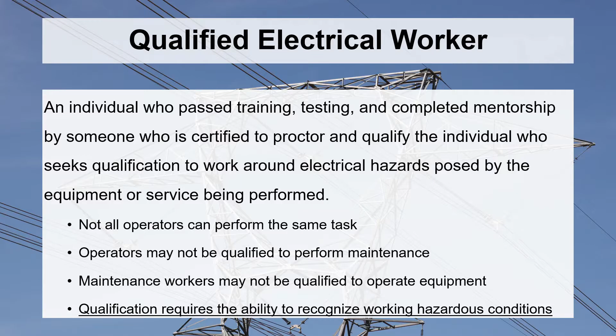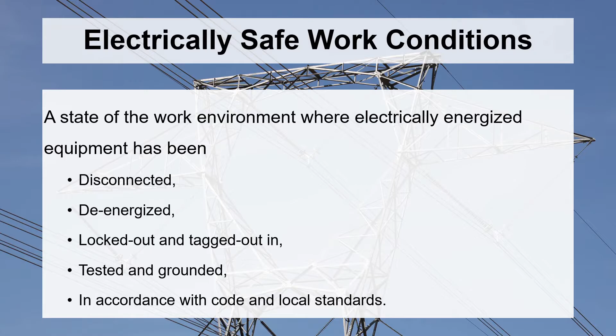Following the principles of electrical safety, creating a safe work environment means that any hazardous energy source is disconnected, de-energized, locked out and/or tagged out if needed, and tested to prove it's in a grounded state, in accordance with local code and accepted standards.